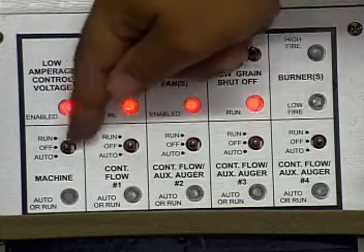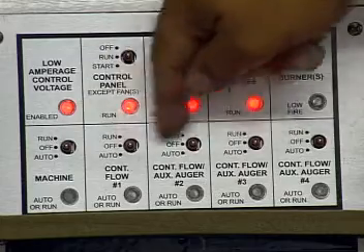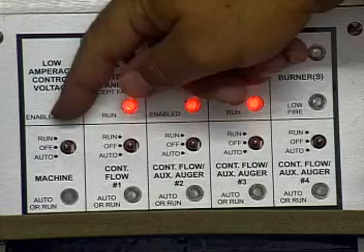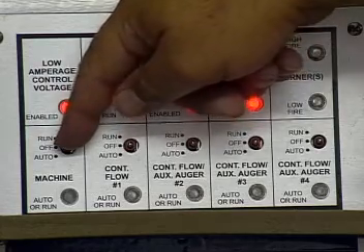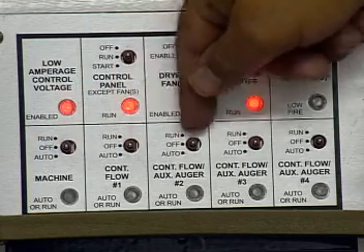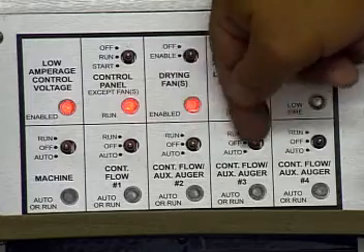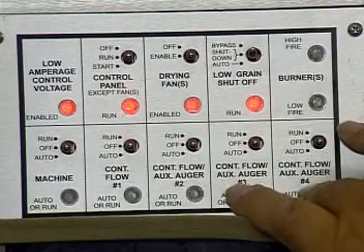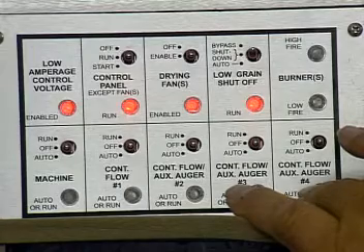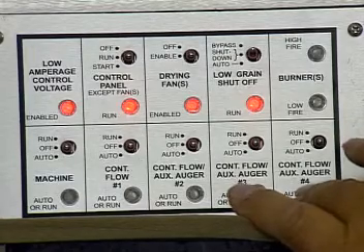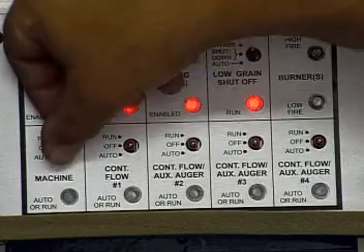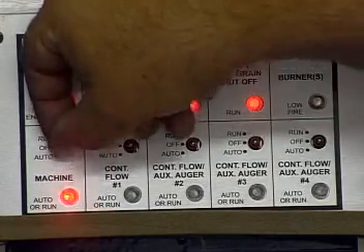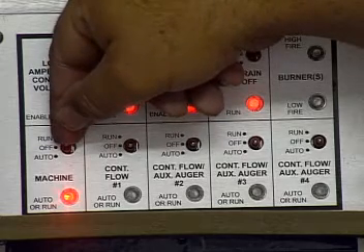The toggle switches in the lower part are all for the machines and the actual motors, and we'll start those motors. This is the one for the circulator itself. This is the one for continuous flow or second continuous flow or transfer, whichever ones you have. A good habit you'd like to get into, and it'll just save you some headaches down the road: every time you start up the computer, take these switches and put them in the run position, which is just like an off and on. You hear the starter engage, and you're going to run the motor for 5 seconds.